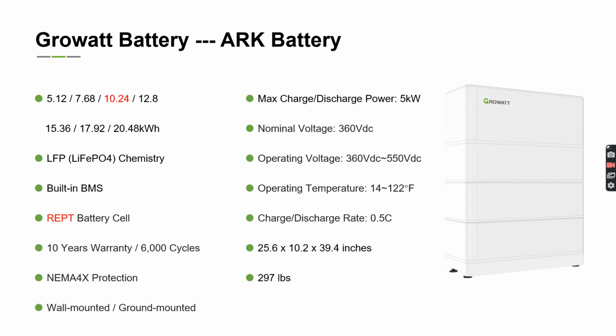Another battery model by Growatt is the ARK battery. This battery will allow for module additions of battery capacity up to 20.48 kilowatt hours. Each additional module will increase the battery bank's capacity by 2.56 kilowatt hours. These batteries will remain operational between 14 degrees Fahrenheit and 122 degrees Fahrenheit and will include a 10-year warranty or 6,000 cycles as well.